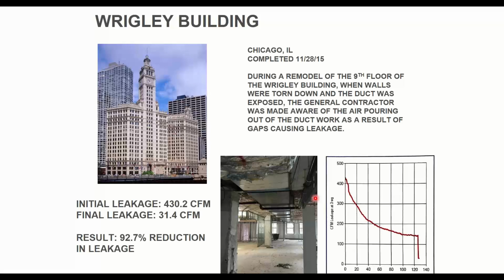Our air handlers do a better job of cooling your building if the air is not leaking all over the place, that kind of idea. So we didn't physically do this work, but we like to get involved in these projects because we're doing other parts of the project anyway. In this case, it was the Wrigley building. It was a small one, very small, only 430 CFM leakage.